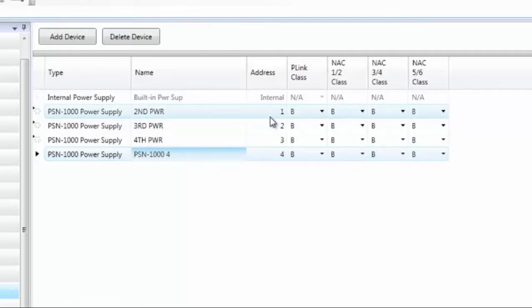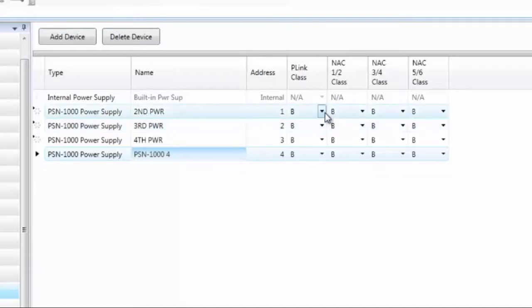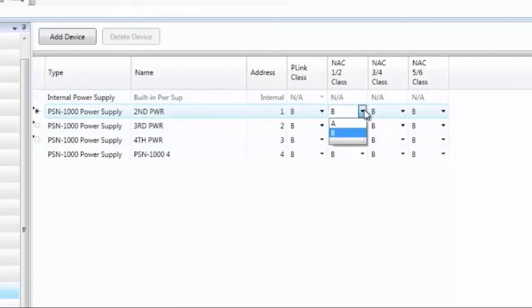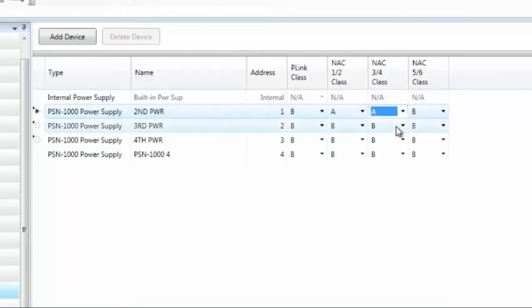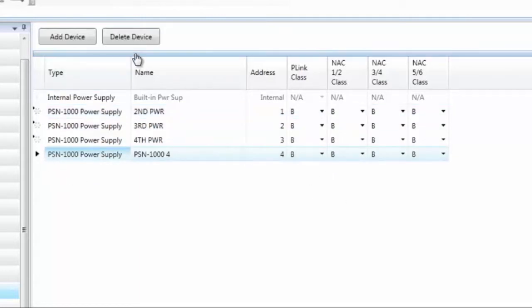The Address column allows you to set the address. These devices have a five-position DIP switch and need some address between 1 and 31, which you can change as needed. You can also designate the class of wiring coming off the PSN-1000. The isolated P-Link repeater can be Class A by switching it to Class A. NAC1 and NAC2 can be Class A, as can NAC3 and 4, and NAC5 and 6 — each is individually configured depending on your project. You can delete devices by highlighting them and selecting Delete Device.